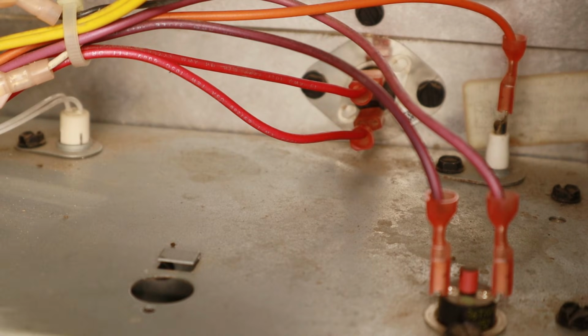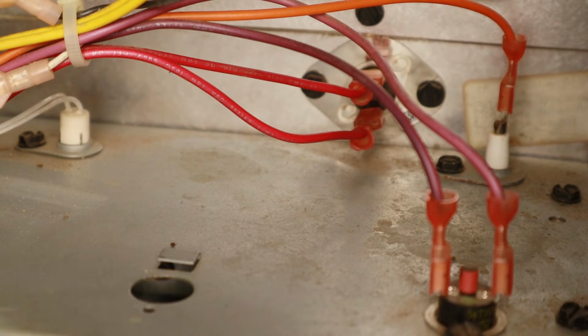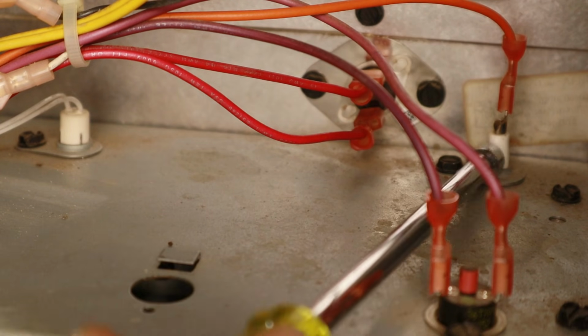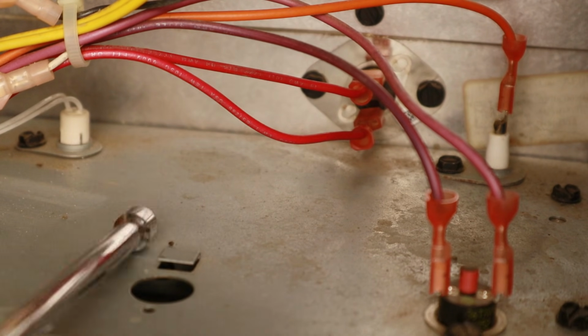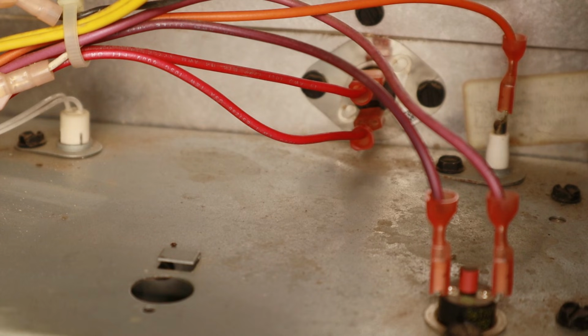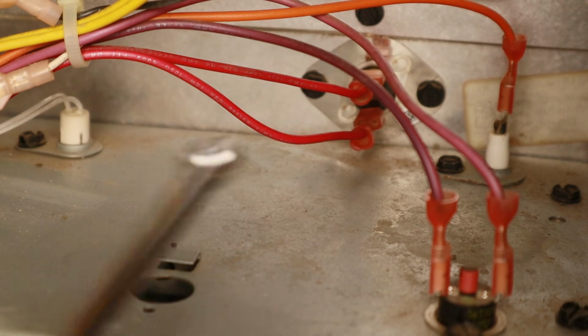So the next step in our sequence, once our inducer motor starts and our pressure switch is proven, is that our hot surface igniter is going to start glowing, which will allow the gas to ignite once the gas valve opens. Now when you look inside, you're going to see two white probes that go down into the area where the gas is introduced through the jets and the flame is ignited.